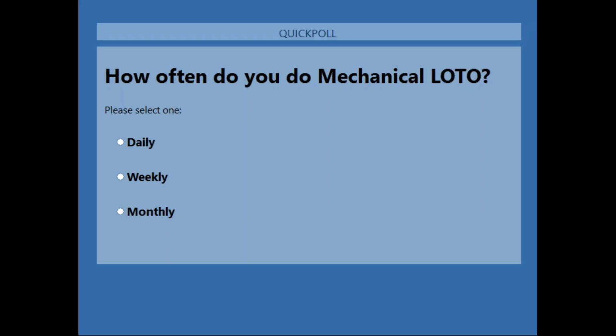But we certainly reduce the likelihood of an arc flash and a shock hazard, and the PESDs identify the voltage sources as required by 70E 120.1 and make sure that you're at the right source. As I go to my next comment, I just want to reach out. How often are you guys doing mechanical lockout tagout in your facilities?